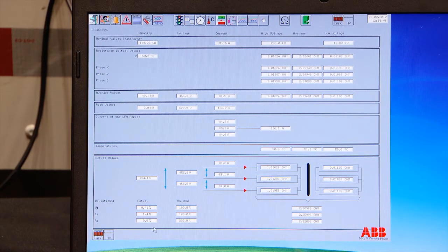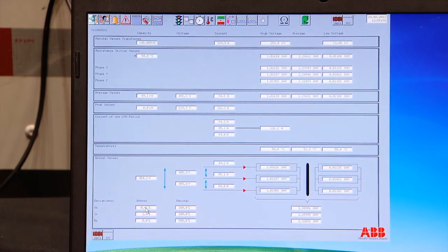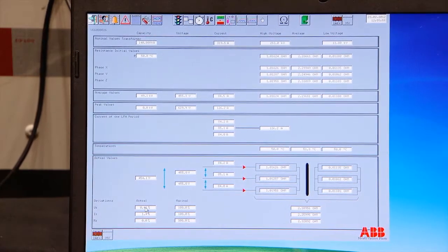In the lower left corner we have the deviation. If you have some kind of problem, some kind of issue with the transformer, you will see deviation in current, voltage and resistance. That's measured in percent. That's a deviation between the windings. If you're feeding it unevenly, or if there's an issue with the tap changer on one phase or whatever it can be, you will see it here.